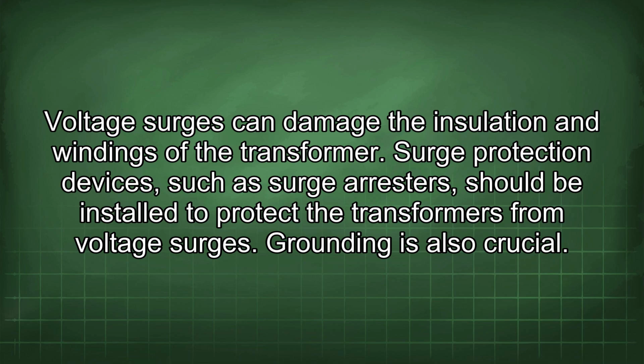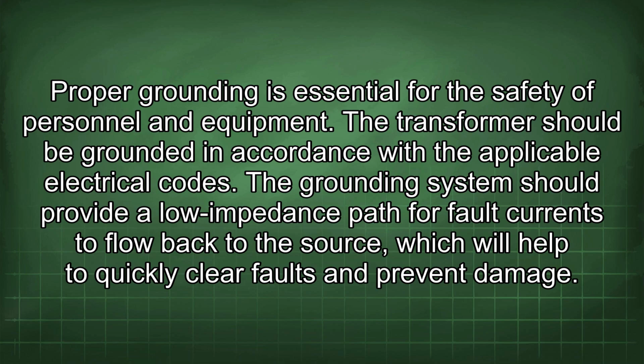Grounding is also crucial. Proper grounding is essential for the safety of personnel and equipment. The transformer should be grounded in accordance with the applicable electrical codes. The grounding system should provide a low impedance path for fault currents to flow back to the source, which will help to quickly clear faults and prevent damage.